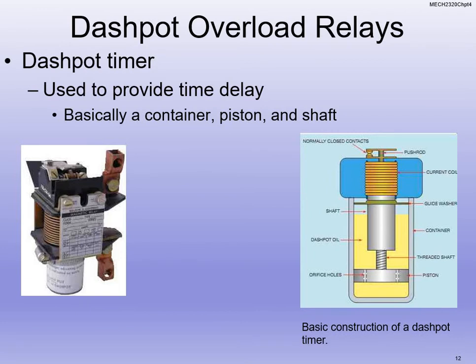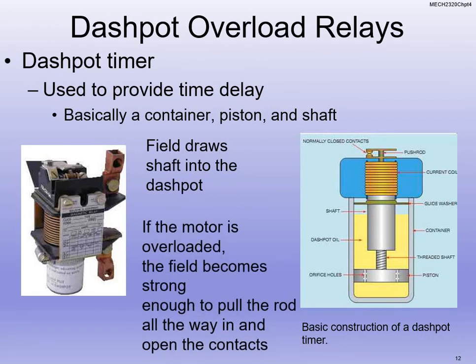But we're using the current itself and the magnetic field of the current to control how far that piston goes. And remember, the oil that's in there is really just to slow down the piston so that it doesn't trip right away, so that it gives that time delay for that inrush current and for the current to level back out to normal operating speed. So that's really what goes on there. And then it has the holes in the piston so that the oil can go through from one side to the other. It's just a single acting type piston.